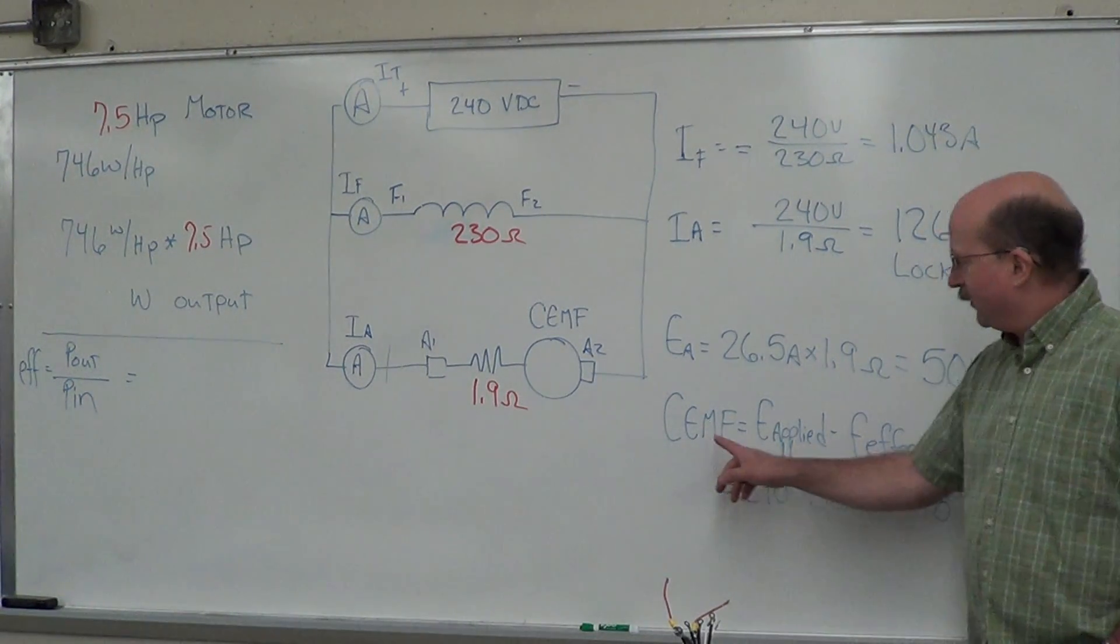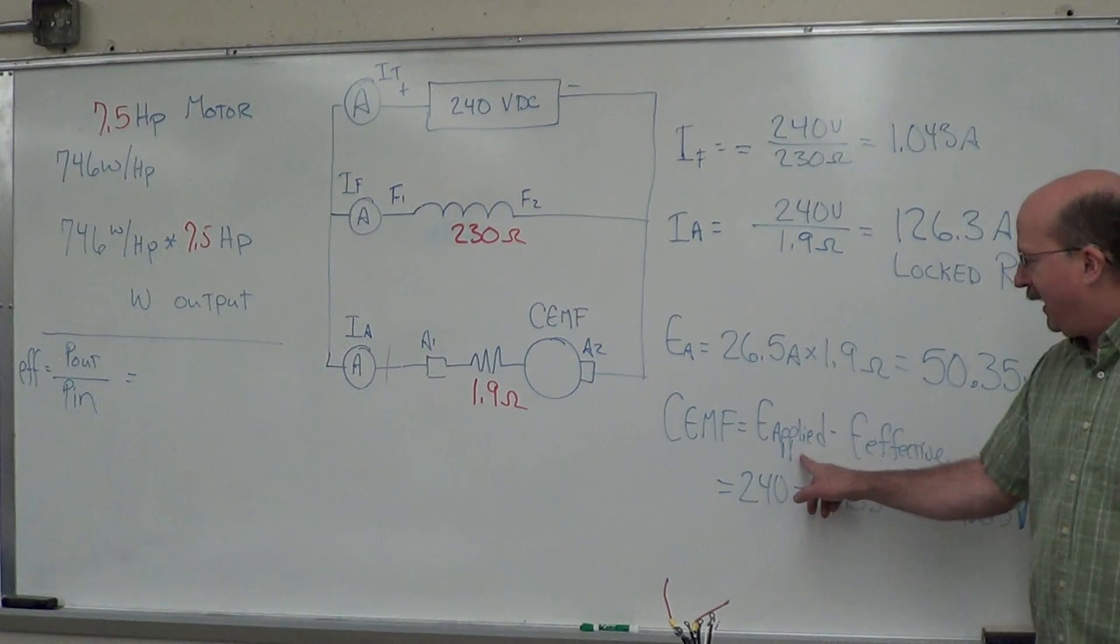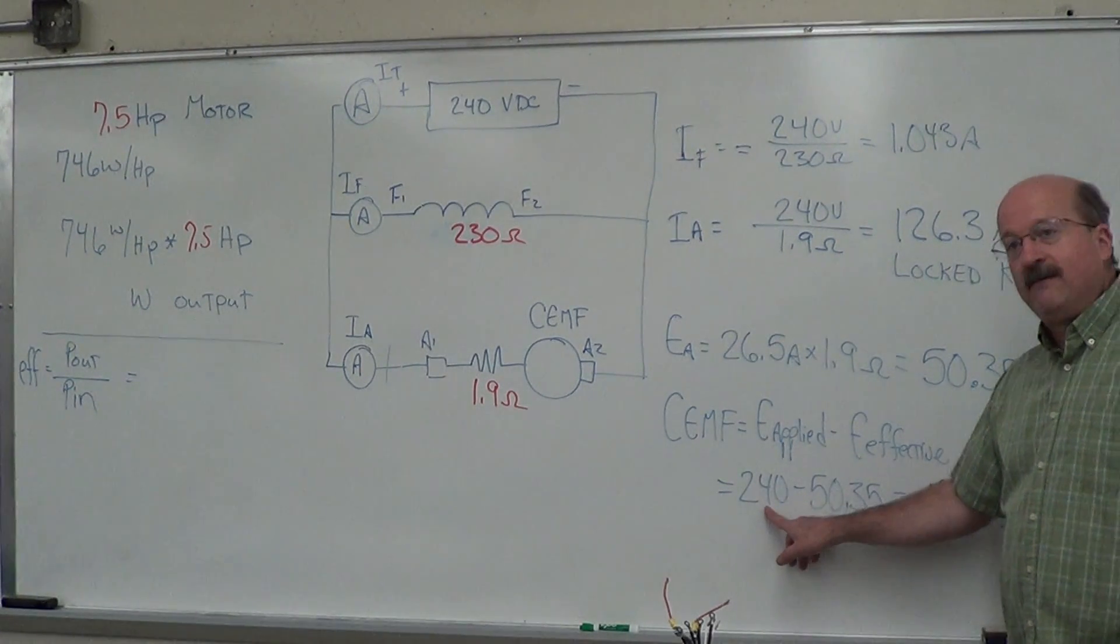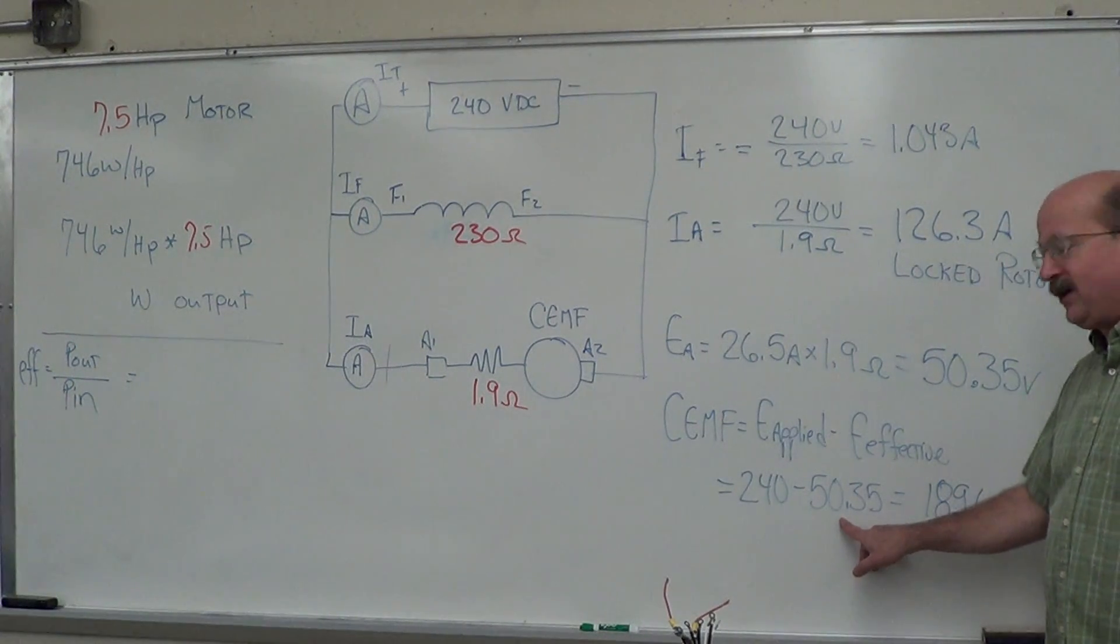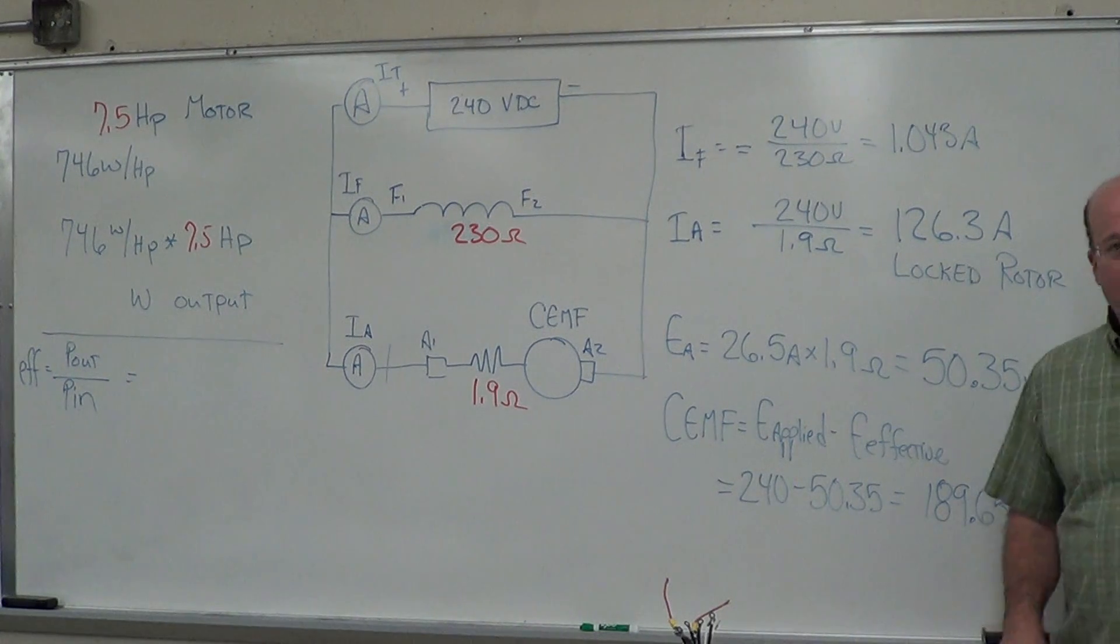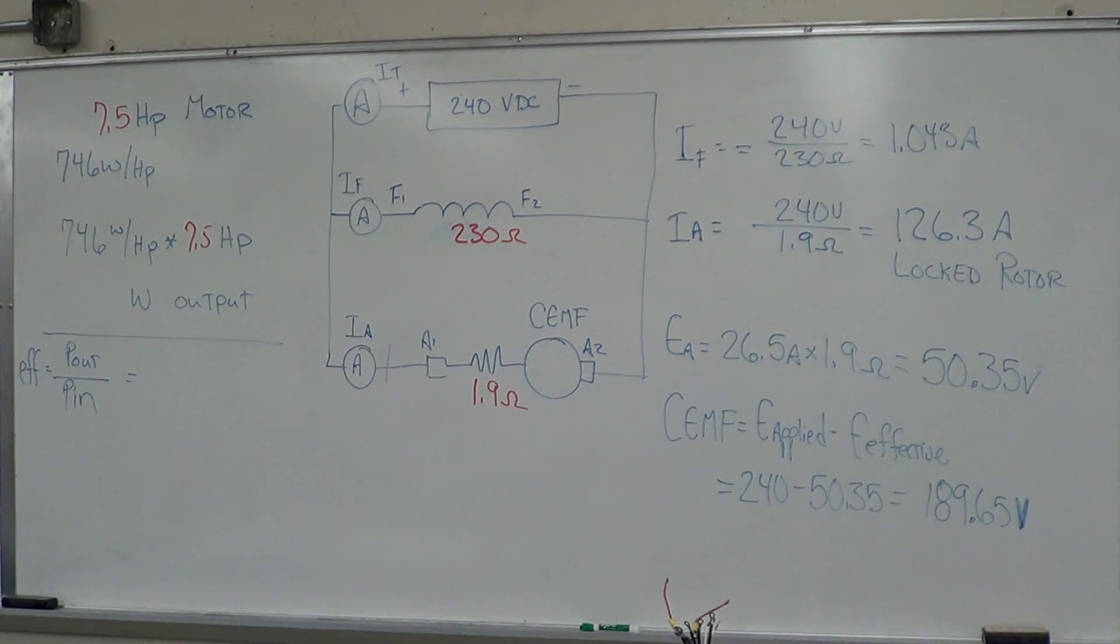That's got to mean there's something else being generated in here to prevent that full 240 volt drop across there. That's our counter-EMF. So if counter-EMF is equal to the applied voltage minus our effective, which is 240 volts minus our 50.35, gets us 189.65 volts, 189.7 volts there.